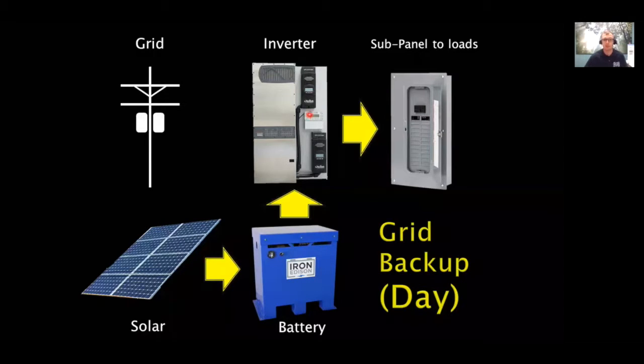Almost every inverter and charge controller we use has these features built in, allowing it to automatically start or stop, get grid charge or gen charge, and do load support, or even peak load shaving, a newer feature. In commercial applications, a business may have demand charges, and we can use these same load-sensing features to offset commercial peak load charges on the electrical bill.